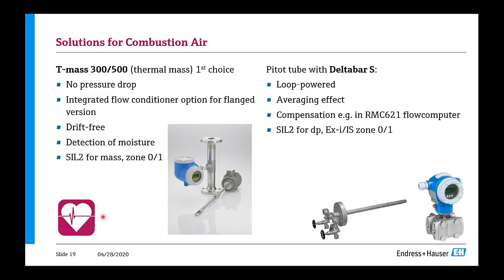So those are our solutions when it comes to combustion air measurements, as I mentioned. Mainly the T-mass 300/500, typically as an insertion device, you will find here. It doesn't have any pressure drop. You have integrated flow conditioner options for the flanged version only. So this is rather for smaller line sizes, but this is maybe relevant for other applications. It's drift-free. You can detect moisture. That's also a beauty. So that's one solution for the former problems of the thermal mass flow meters. And only wait a few weeks or months, and this one is available.